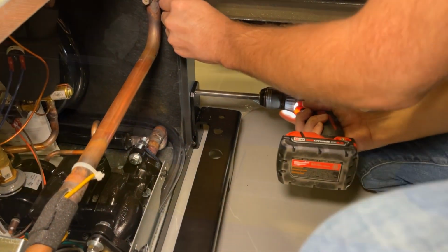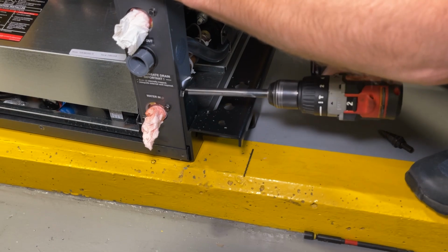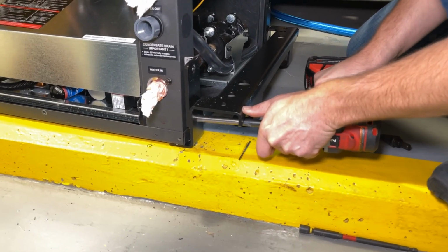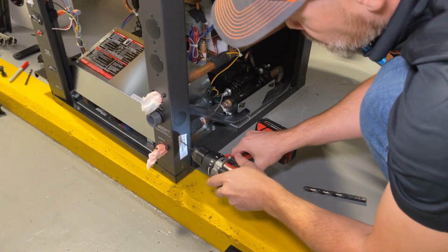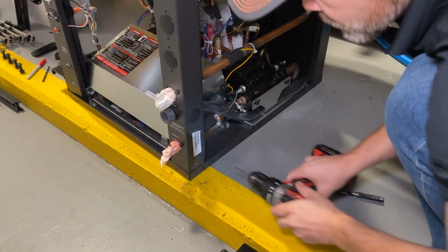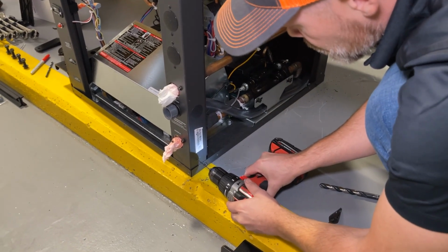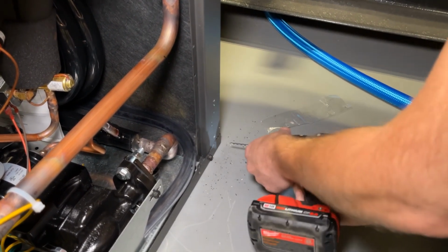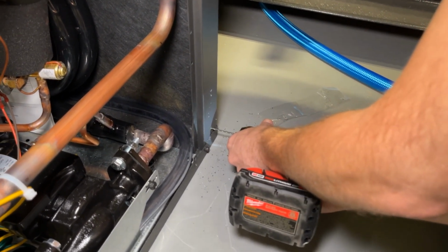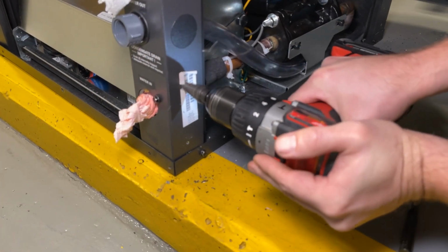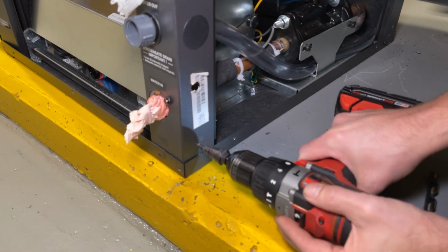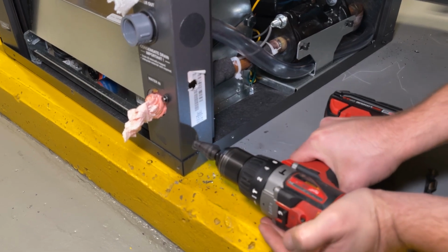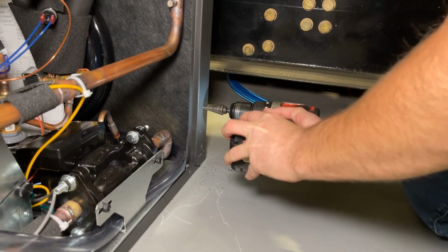Position the bracket flush with the exterior and use a 1/2 inch drill bit to mark the location of each hole. Next, use a 1/4 inch or smaller drill bit to penetrate the metal. This hole will be used as a guide for drilling the finished hole. Once the guide hole is drilled, use a 3/16 to 1 3/8 inch step bit to enlarge the guide hole to the finished size of 1/2 inch.